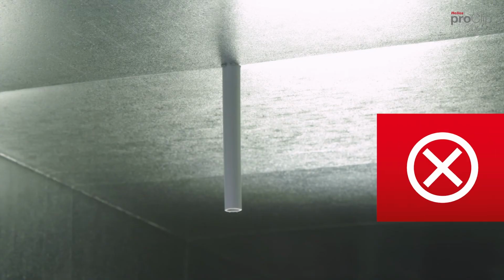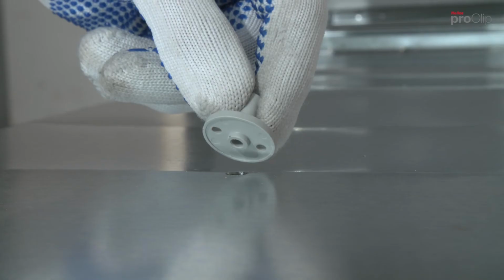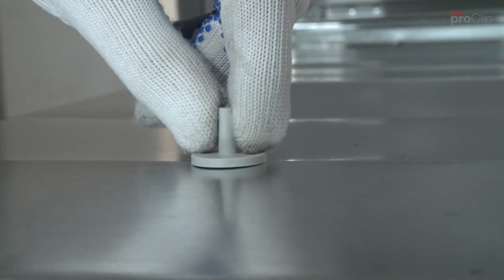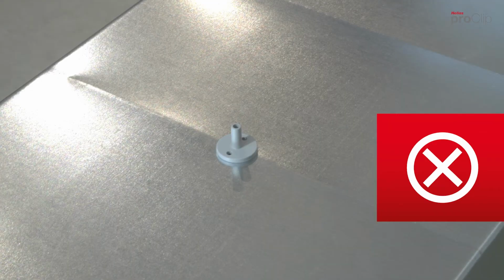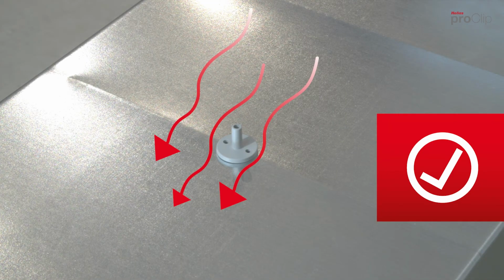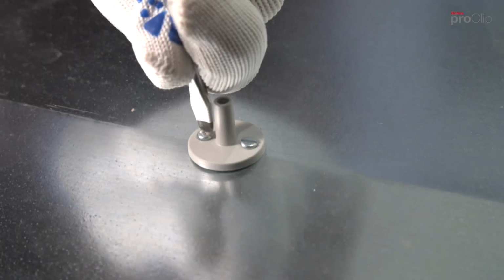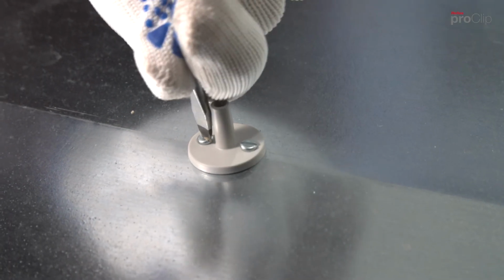Shorten the measurement probe so that it is flush with the inner wall of the ventilation duct. When attaching the measurement probe, ensure the correct alignment of the screws with the airflow. Also make sure that the drill hole is properly sealed.